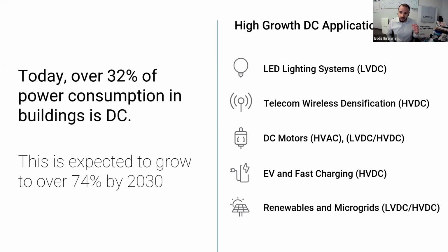From the bottom up, that's our consumption. What's happening at the grid level is that transmission grids are also moving to ultra high voltage direct current. Think of any new transmission-level power line, not distribution. There's a break-even distance of about 500 to 600 kilometers, above which it has to be direct current. There's no way to do alternating current cost effectively beyond that.